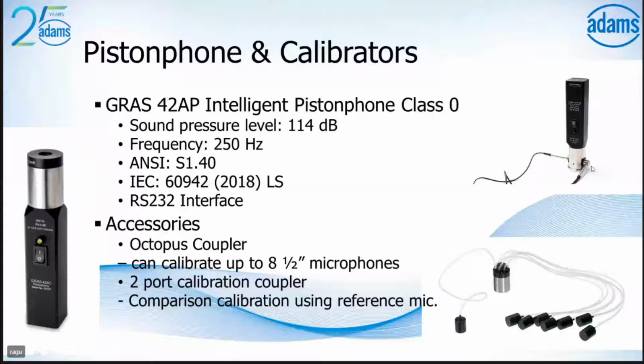So this octopus coupler can be connected with the piston phone, and you can check 8 half-inch microphones at the same time using the 42AP. So if you're going to do a multi-channel data acquisition for an acoustic data acquisition system or measurement, like you're going to use more than 4 channels or up to 8 channels, you can use this octopus coupler.